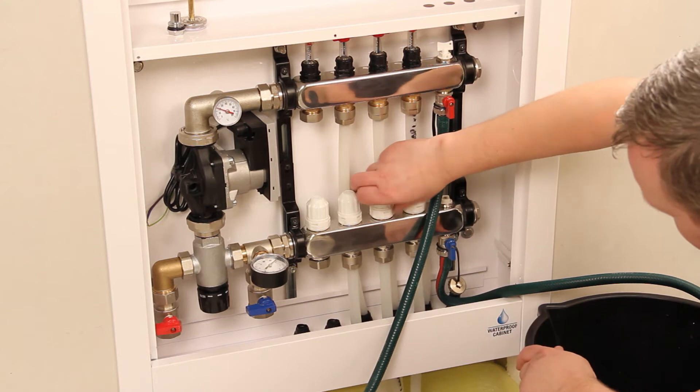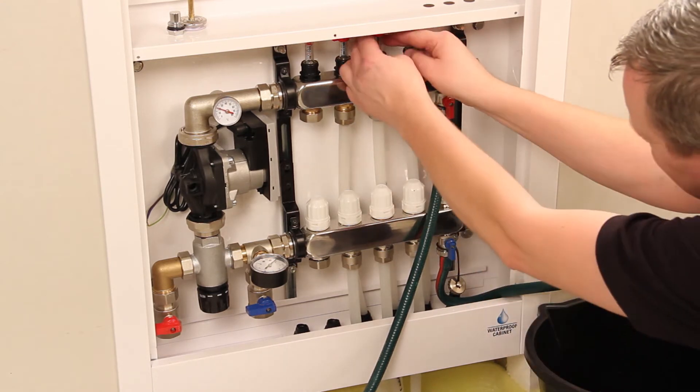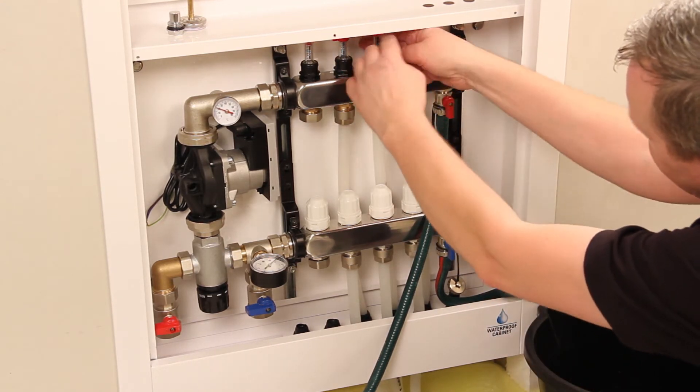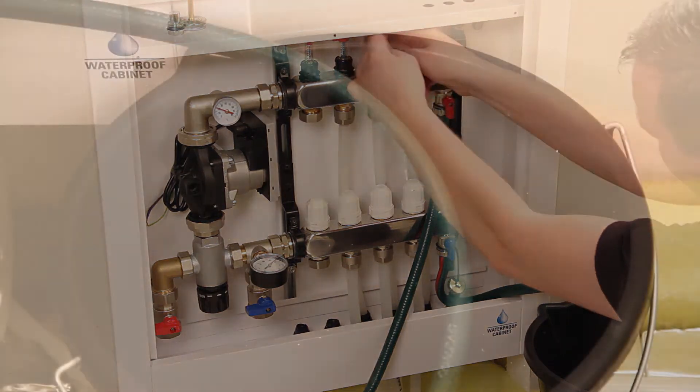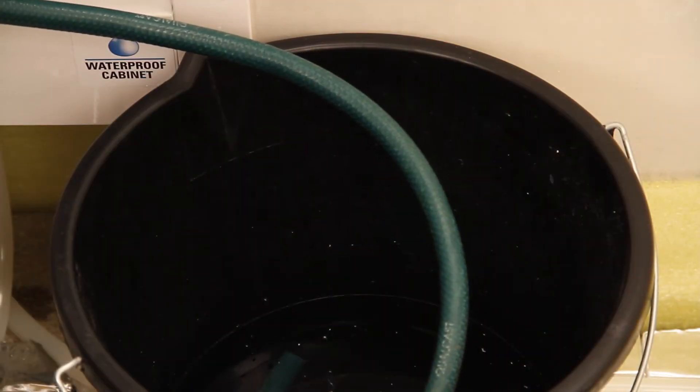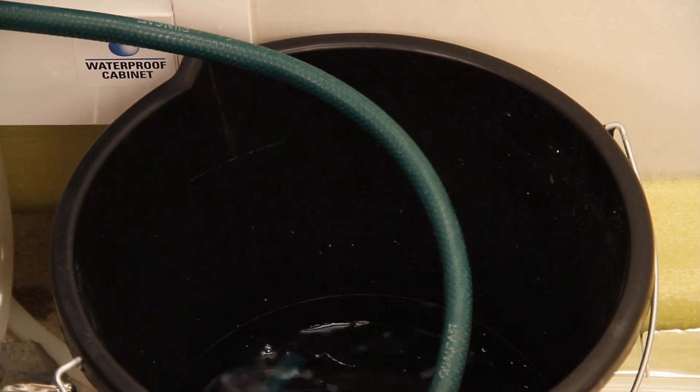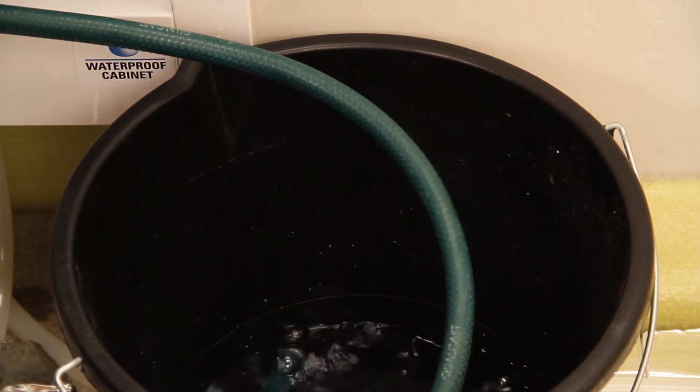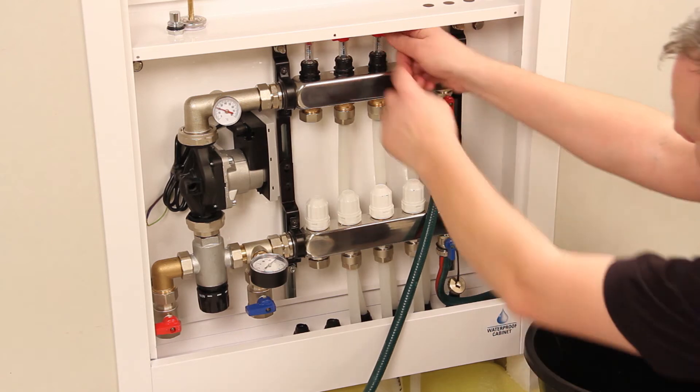Repeat this sequence opening the flow gauge and return valve for each individual circuit of pipe one at a time, purging all the air from the pipe and filling with water. Don't forget to keep an eye on the water level in the bucket and empty in between commissioning each circuit of pipe.